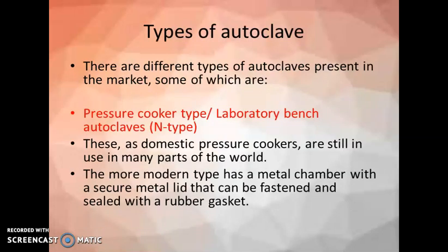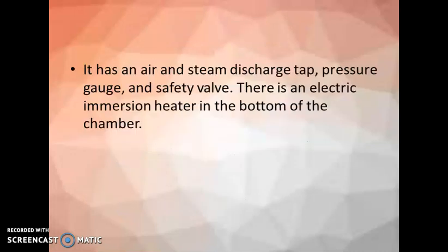Next is about types of autoclave. There are different types of autoclaves present in the market, some of which are the pressure cooker type or laboratory bench autoclave. This type is most commonly used in our colleges, hospitals, etc. Domestic pressure cookers are still in use in many parts of the world. The more modern type has a metal chamber with a secure metal lid that can be fastened and sealed with a rubber gasket. It has an air and steam discharge tap, the pressure gauge and safety valves, and also an electrical immersion heater present at the bottom of the chamber.